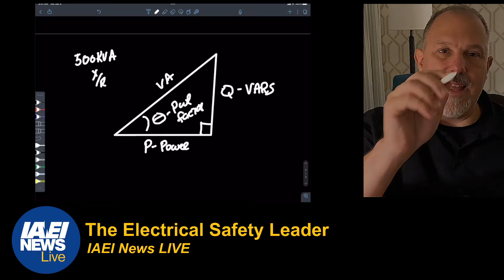Now, transformers will be published with an X to R ratio — they'll tell you what the X to R ratio is, and that's basically giving you that number so you can calculate theta. We're going to get to the equations for this transformer, but I want you to understand the practical application of what we're going to discuss from a math perspective, because you need to know power factor. Power factor is that angle.